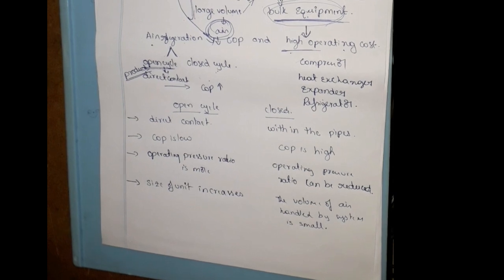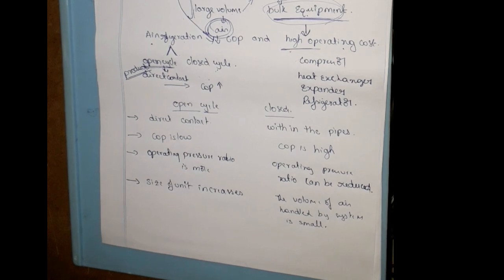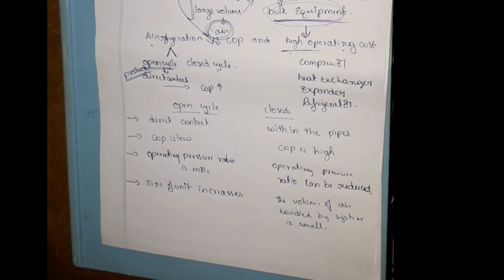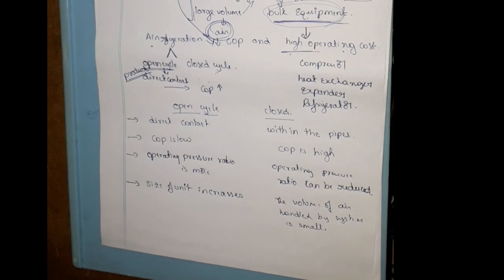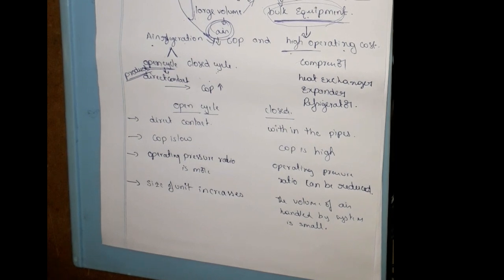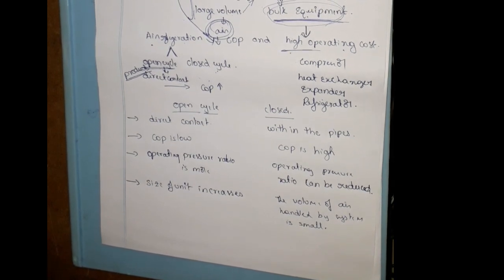Open system, first point: air comes in direct contact with the refrigerated space. Closed system, first point: air gets circulated within the system without coming in direct contact with the refrigerated space. Second point: in open system, the pressure of the air is atmospheric in the refrigerated space; in closed system, the air is dense. Third point: in open system, the volume of air handled by the compressor and expander is large, and thereby the size of the unit increases; in closed system, the volume of air handled is small. Fourth point: COP is low in open system, COP is high in closed system. Operating pressure ratio is more in open system; in closed system, the operating pressure ratio can be reduced.